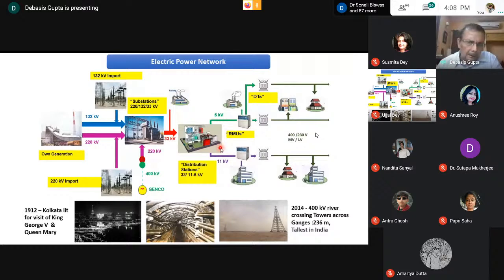Then you have a scenario true throughout India: before the distribution station, you have the substation I mentioned. Substations are typically 200 MVA, 220 MVA, 250 MVA, 300 MVA size. Then you have distribution stations, which step down from 33 kV to typically 11 kV in 90-99% of cases. Only in CESC do we also have 6.6 kV, a legacy British handover. These stations are typically 10 MVA, 20 MVA, 16 MVA in size.